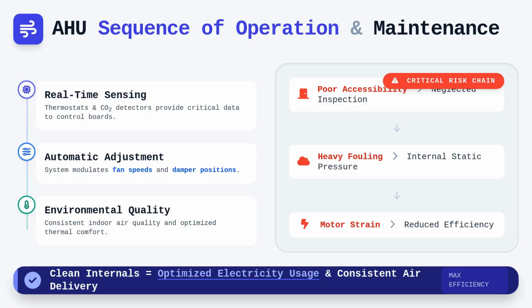From a cleaning and maintenance perspective, accessibility is the primary challenge when dealing with these complex internal layouts. If components like the blowers, dampers, or heat exchangers are not easily accessible, they often escape routine inspection, leading to heavy fouling that forces the motor to work harder to overcome internal static pressure. By maintaining a clean internal environment, the specialist directly impacts the overall operational efficiency of the building, ensuring that electricity usage is optimized and the air delivered remains consistent.